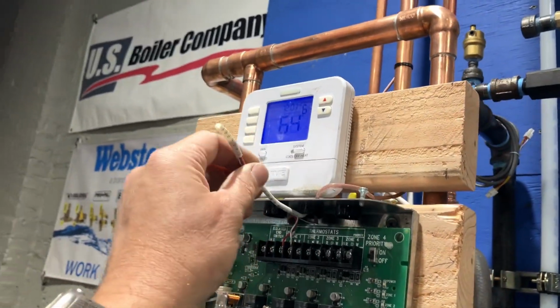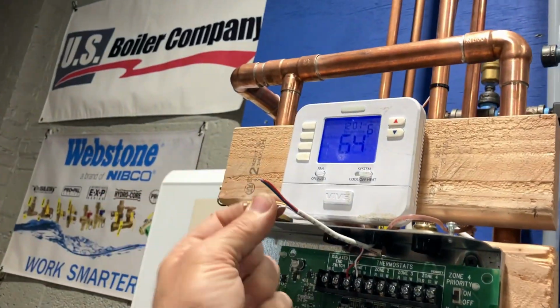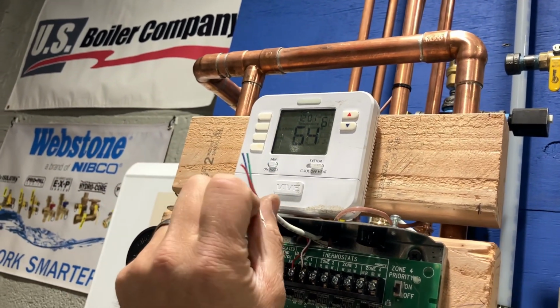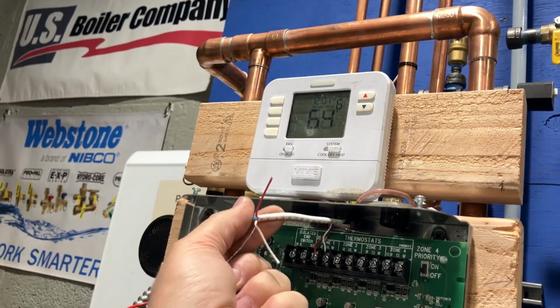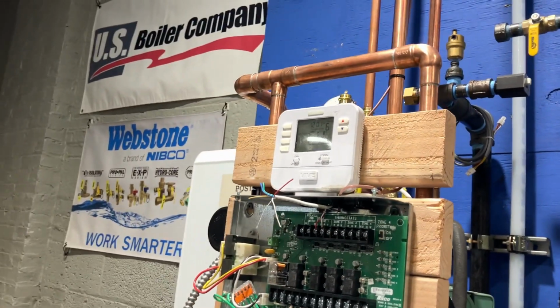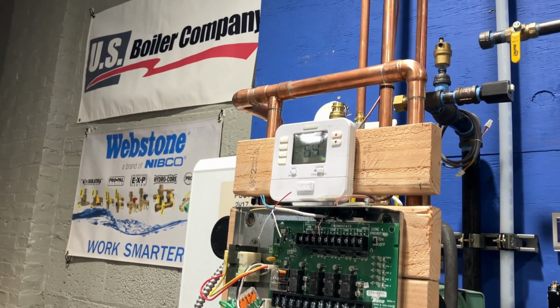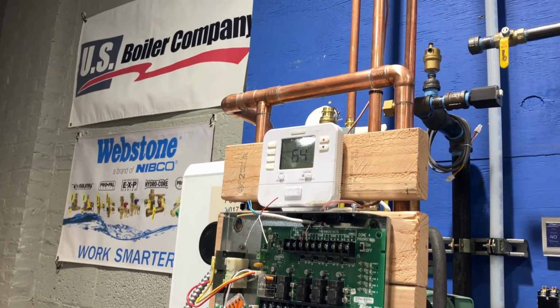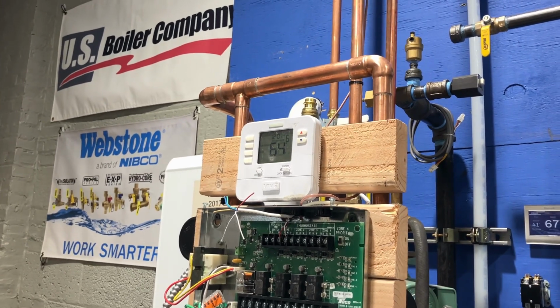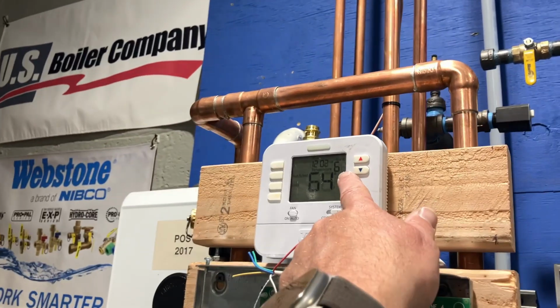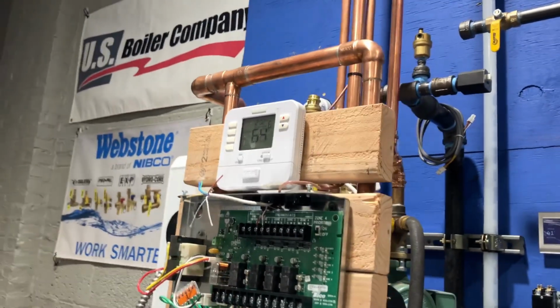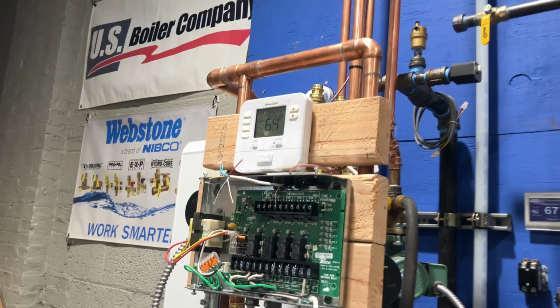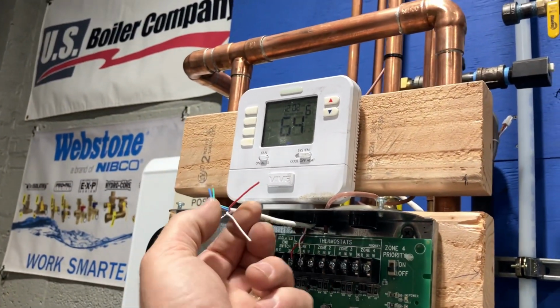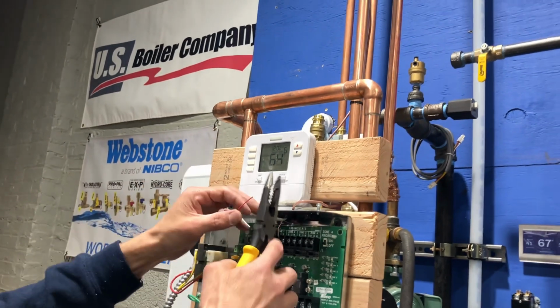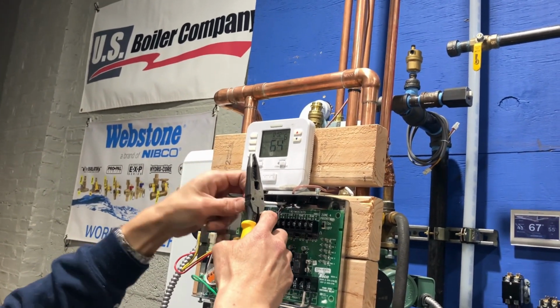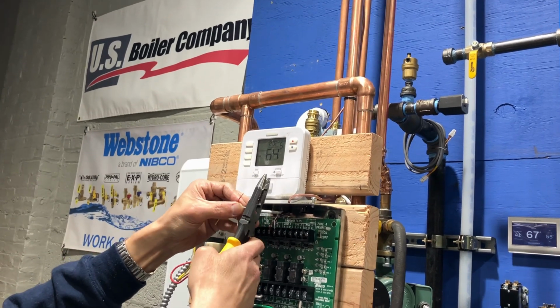Now, on the opposite end of the thermostat wire between R and W, would this circuit be open or closed right now? Right now with the heat on, I thought you just told me it would close the circuit. It would link the two wires together. Wrong answer. A good technician is observant of his surroundings. The set point is 61, it's reading 64. So the circuit is open, off. Correct. Now, I want you to strip away a little bit of the insulation on the red and the white wire, and then we're going to test for continuity on R, H, and W.